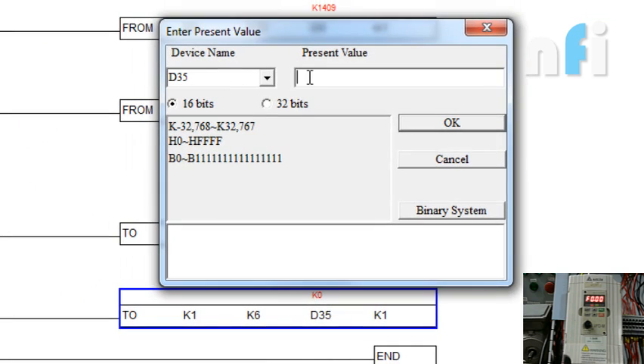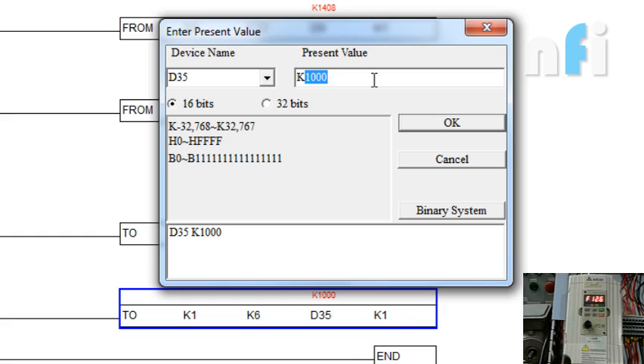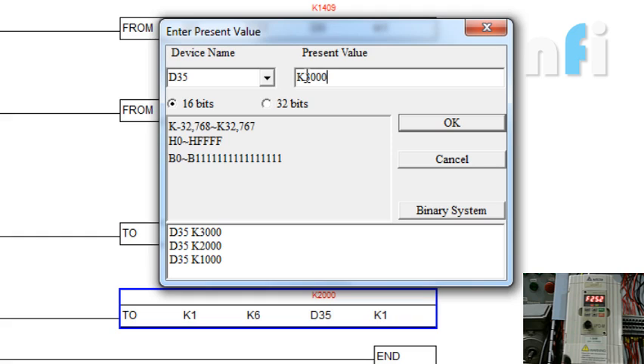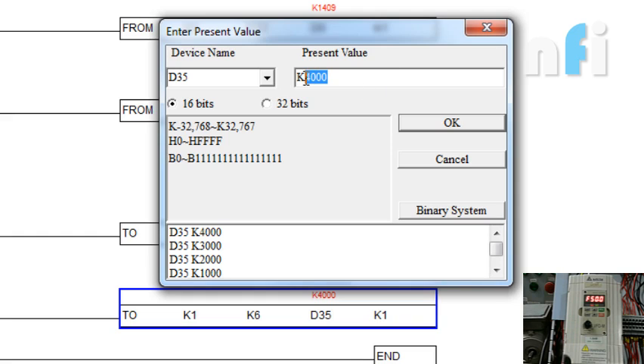Now D35 is initially 0, so my frequency is 0. If I change this value to K1000, you can see the output 12.5 Hz. 2000 would be 25.2. 3000 would be 37.5. 4000, that's 50 Hz.